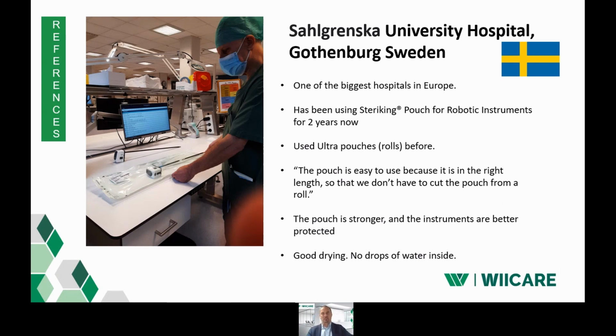So they don't need to think about it, but they always just put any instrument into the pouch and then can seal it. They also told that this pouch is stronger than normal pouches, so it's protecting the instruments much better, and that there are good drying properties. So in the autoclave, you have the drying cycle in the end, and it's important that there will not be any water drops inside.